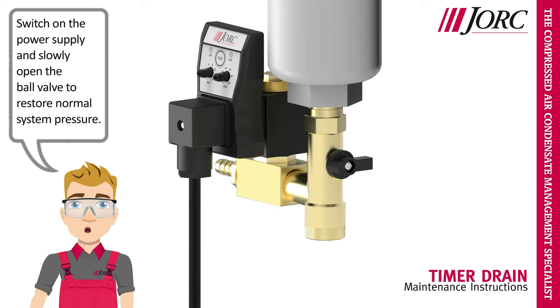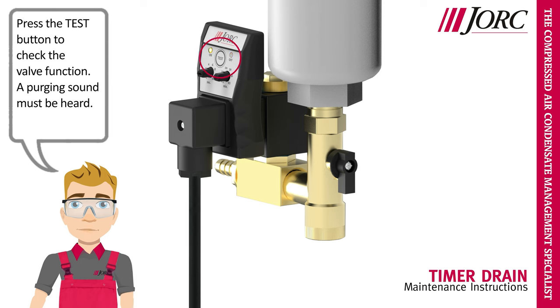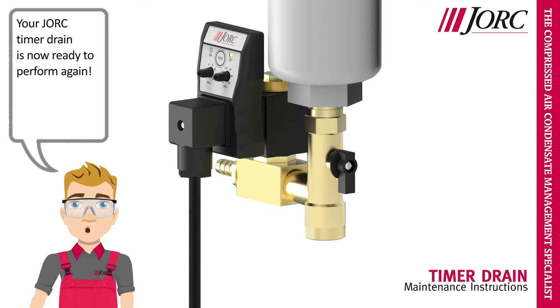Switch on the power supply and slowly open the ball valve to restore normal system pressure. Press the test button to check the valve function — a purging sound must be heard. Your JORC timer drain is now ready to perform again.